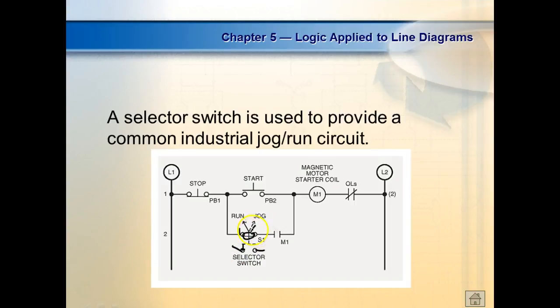So if I switch it over here to this position, then when I press the button, this contact's going to close, but this circuit down here, we don't have a seal-in anymore. You understand? So I can hit run and jog the motor. If I put it over here and then hit start, it's going to seal in. So this is a run-jog circuit.